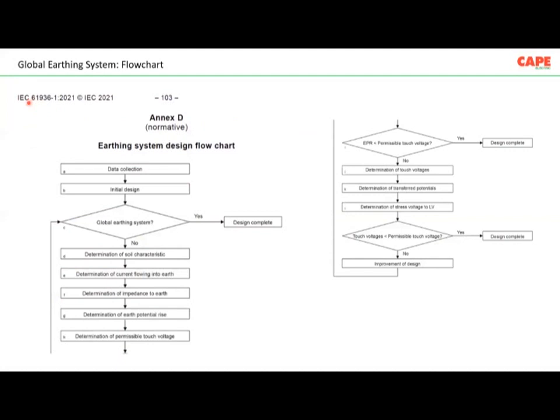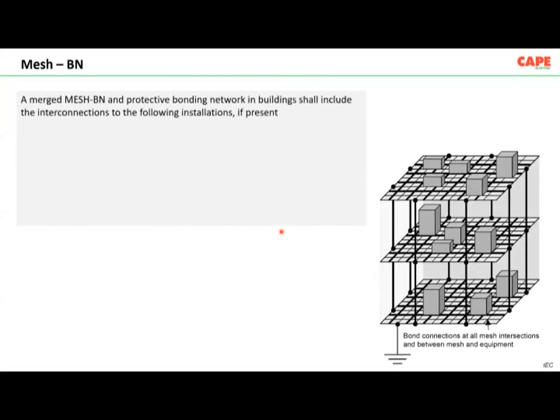I'm just showing you the page from the risk assessment page from the IEC 61936. Earthing system design flowchart, data collection, initial design, global earthing system. Yes, design complete. If you are doing a global earthing system, you don't need to do all these parameters such as soil characteristics, current flowing to earth, impedance to earth, earth potential rise, permissible touch voltage. All these calculations are simply not required. You just go for a global earthing system, but ensure that the shock voltages are reduced to less than the limit, which I have shown in one of the slides.